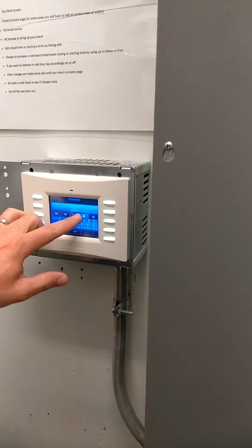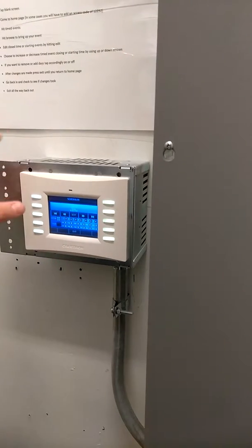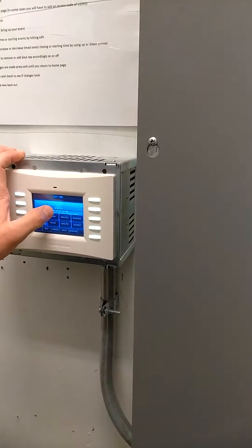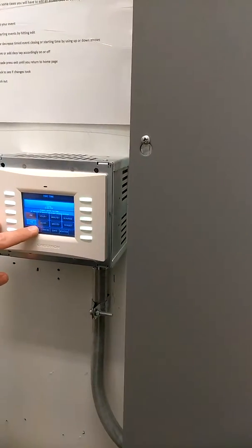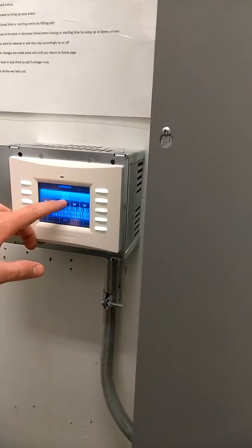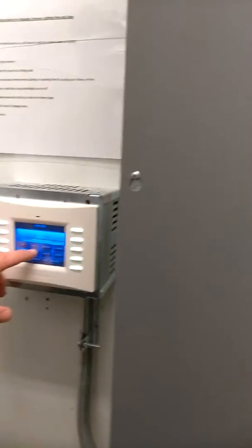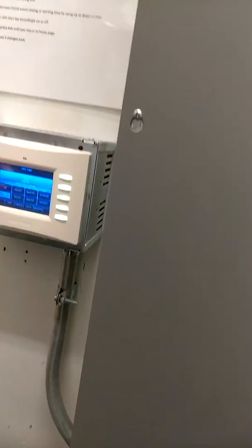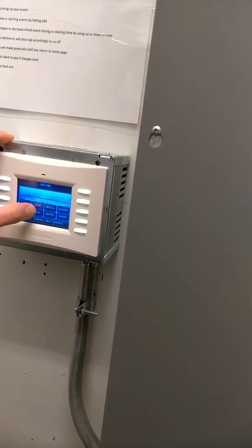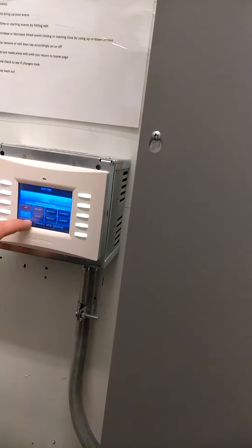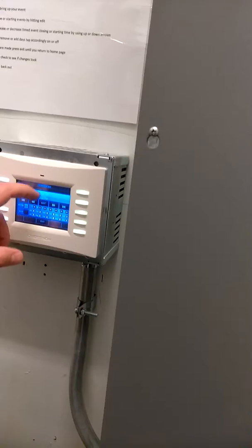So I'm going to go back and put that back, unless... The next event is called Cafe Off, and right now it's set to fire at 4 p.m. Let's say we wanted that to be at 5 p.m. You hit edit, and hit hour plus, and you see it change to 5 p.m. there. And hit exit, and now it will fire at 5 p.m. daily. What time would you like the cafe to turn off? It was set for 4 last time I was here. Yeah, sometimes they have an event and I had to erase it. So maybe 7, okay, 7, 8. So that's 7 p.m., and we'll hit exit.